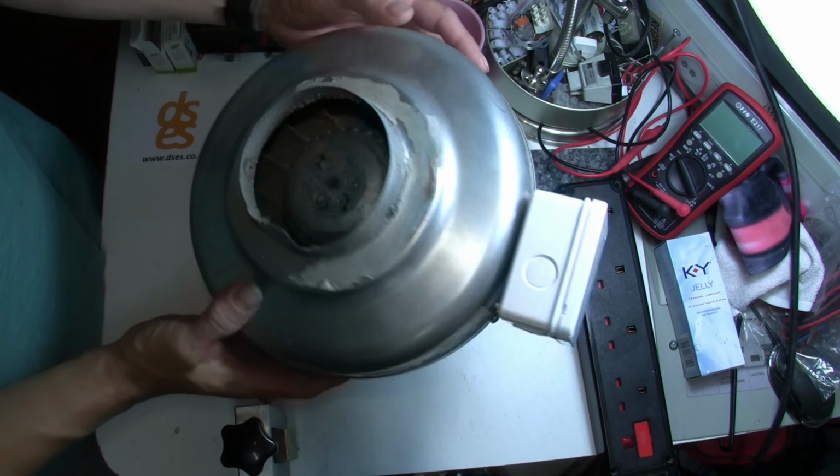The electrical arrangement by how this worked was somewhat clumsily installed by being shoved into a large IP enclosure on flying leads hiding in the void near the fan, but I was able to access it and break it down. And look, I've even built a little demonstration mock-up for you. On the left is the light and switch for bathroom 1, on the right is the same for bathroom 2. The extractor, represented here by this equipment fan, will operate when either light is switched on.